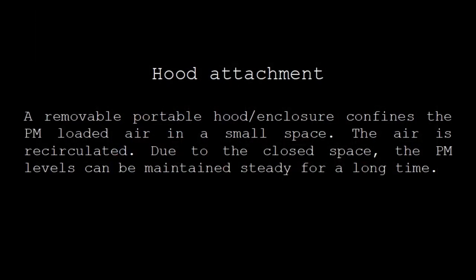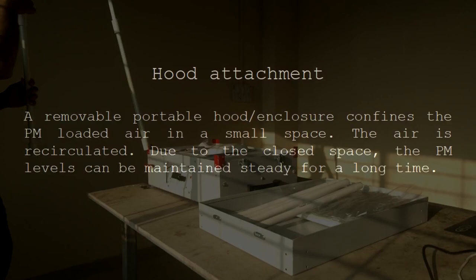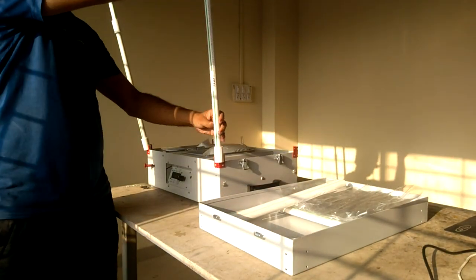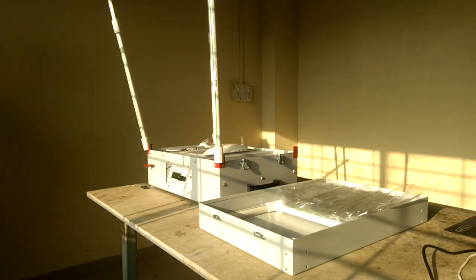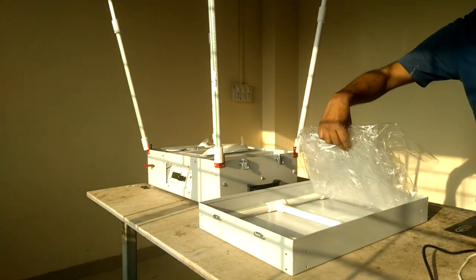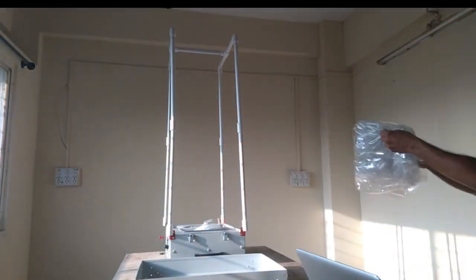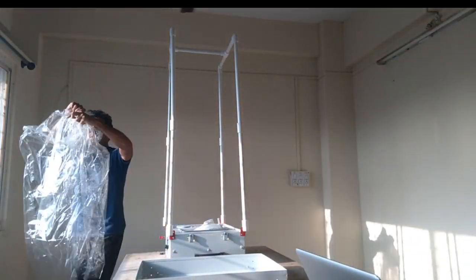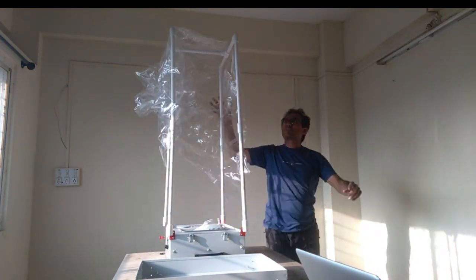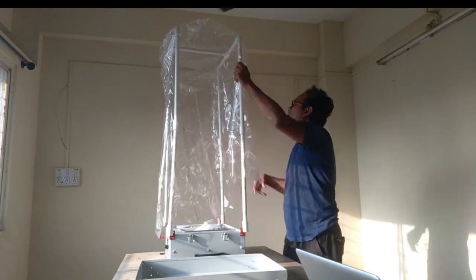One aspect of this system is to have a closed enclosure. The enclosure helps to achieve and maintain a consistent air quality. This quality is necessary for testing different masks at different conditions. The limited enclosure volume also allows for varying the PM 2.5 levels quickly as per requirement.